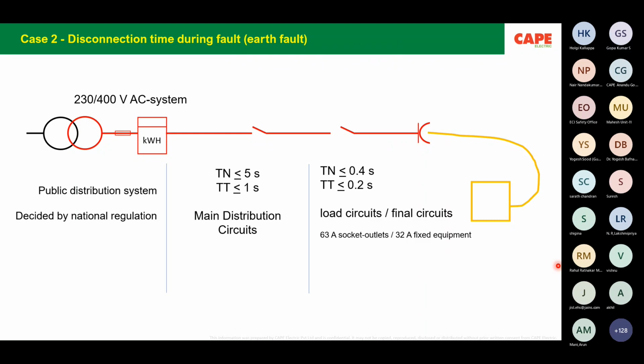Disconnection time, case number 2. Disconnection time means the time in case of any fault. Please note that there are two subjects, short circuit and earth fault. Wherever fault is mentioned, it means an earth fault: an insulation breakdown between a live conductor and earth is a fault, whereas a short circuit between current carrying conductors is called a short circuit or overcurrent.